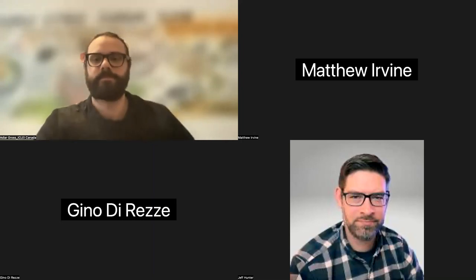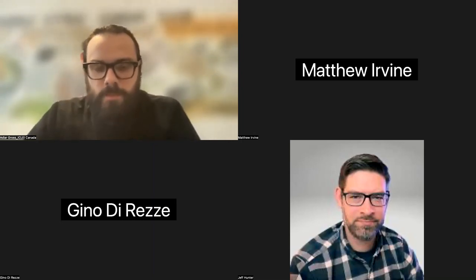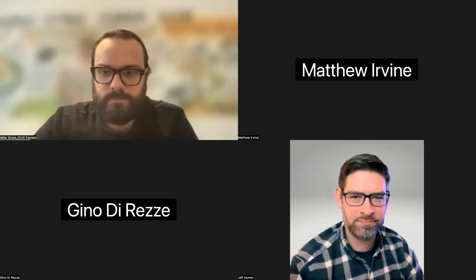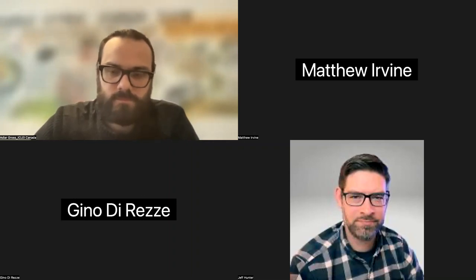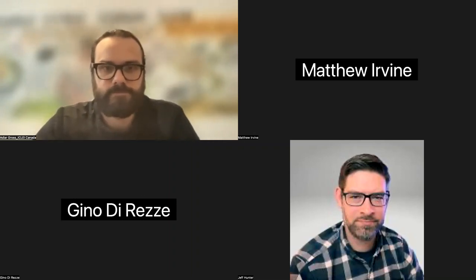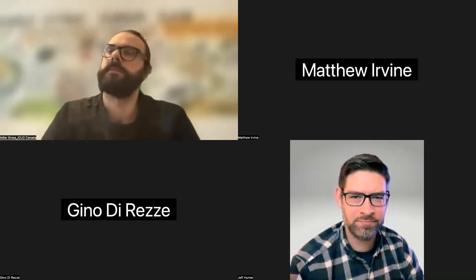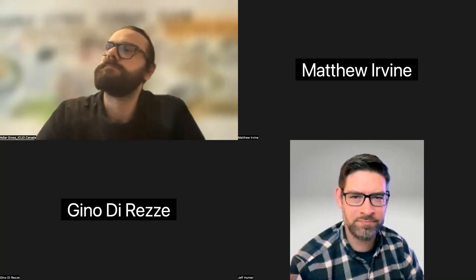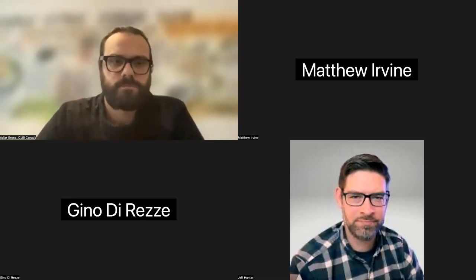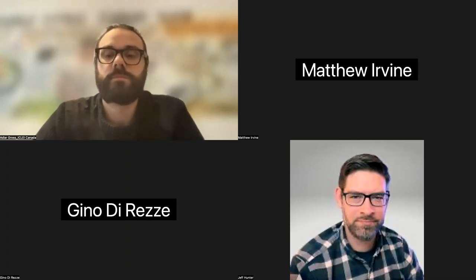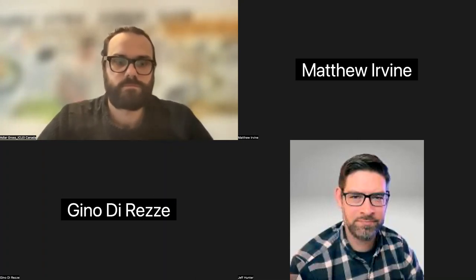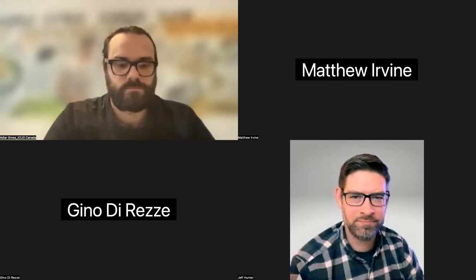Yeah, sure. I don't want to hold myself out as a natural gas air source heat pump expert. I would say, and I think Jeff and Gino would agree with me, air source heat pumps have come a long way in the past 10 or 20 years. Having cold climate air source heat pumps with decent performance, a COP of 1.5 down to minus 25, is an improved air source heat pump. But I would also point to Jeff's chart that outlined the load on the grid. Obviously, the electrical load on the coldest day of the year is reduced if you're backing it up with gas. By backing it up with gas, you're not really moving towards this decarbonization of the electricity grid.